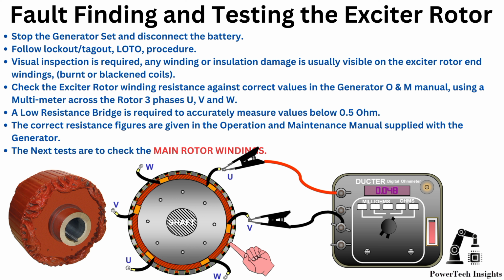Check the exciter rotor winding resistance against correct values in the generator O and M manual, using a multimeter across the rotor 3 phases U, V, and W. A low resistance bridge is required to accurately measure values below 0.5 ohm. The correct resistance figures are given in the operation and maintenance manual supplied with the generator. The next tests are to check the main rotor windings.